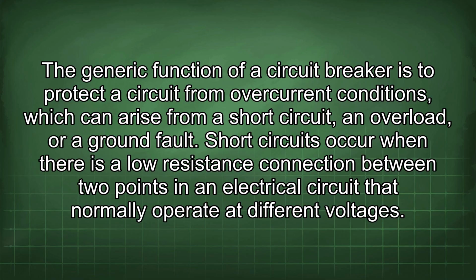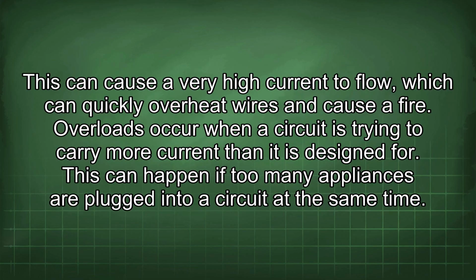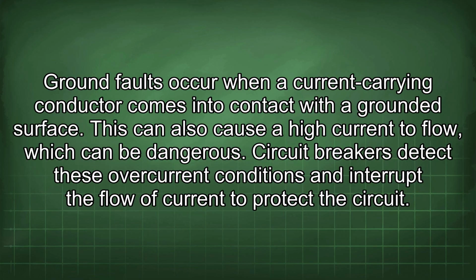Short circuits occur when there is a low resistance connection between two points in an electrical circuit that normally operate at different voltages. This can cause a very high current to flow, which can quickly overheat wires and cause a fire. Overloads occur when a circuit is trying to carry more current than it is designed for. This can happen if too many appliances are plugged into a circuit at the same time. Ground faults occur when a current-carrying conductor comes into contact with a grounded surface. This can also cause a high current to flow, which can be dangerous. Circuit breakers detect these overcurrent conditions and interrupt the flow of current to protect the circuit.